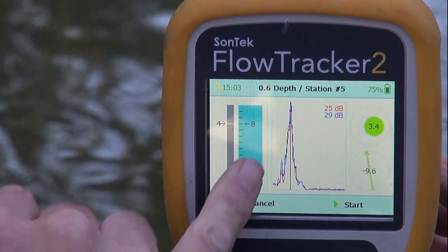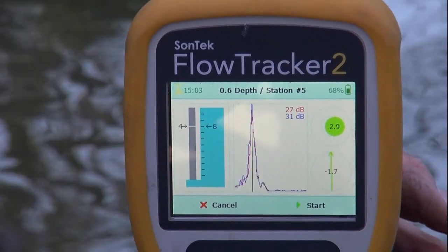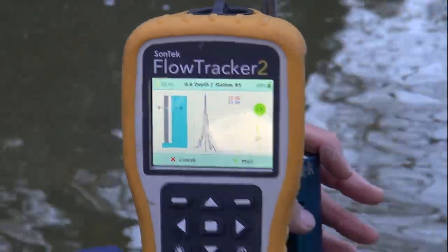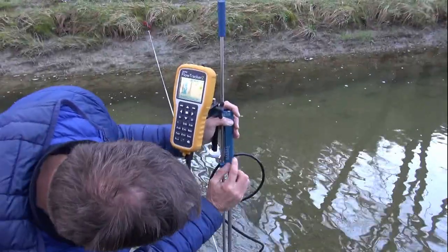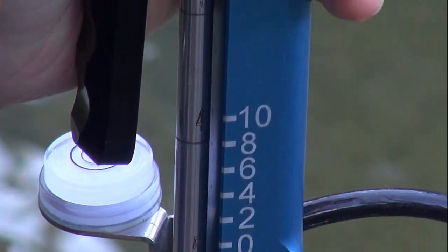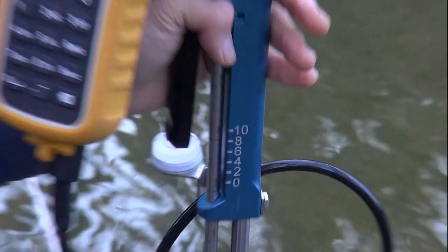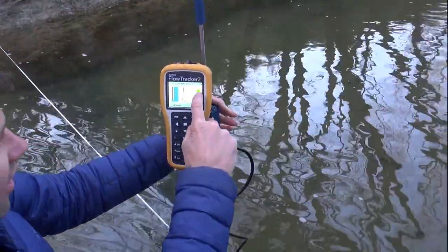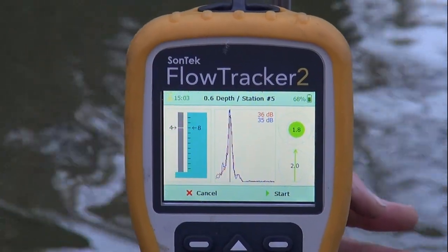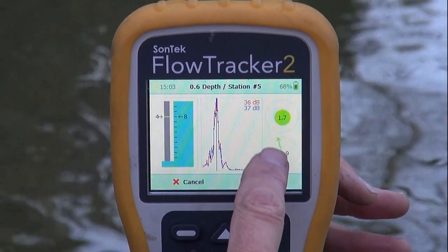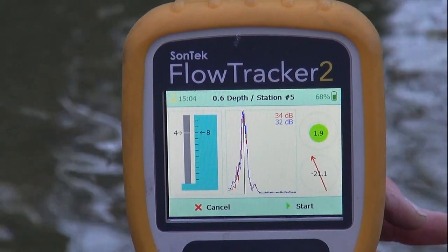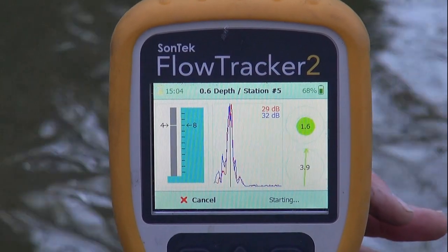We've got our top setting rod summary, so we can adjust that. So 0.48, we want to put the 4 on the round rod, on the 8 on the front scale. So very small adjustment from the last one, but let's be accurate. Check our vertical bubble, so we're still green, and we've got this nice perpendicular flow profile. So we hit our start button.